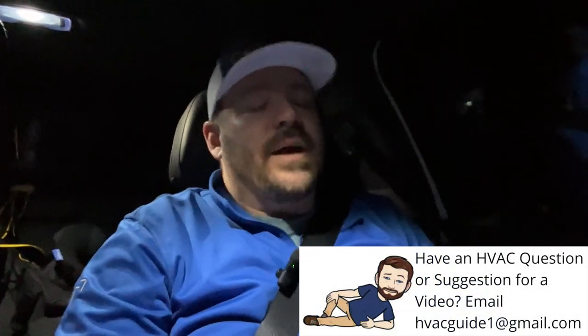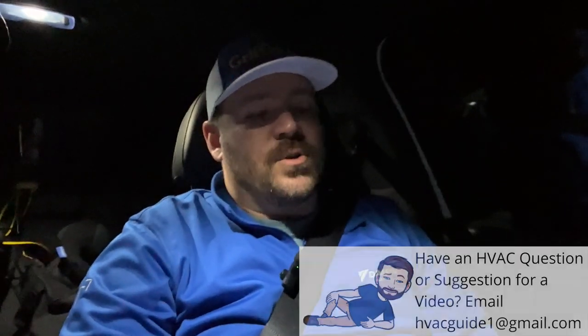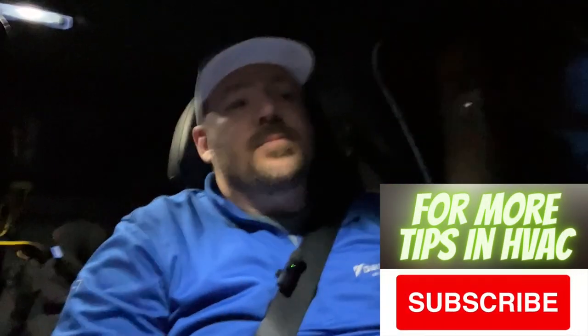I feel like I got a little more technical than I usually do in my videos, but I wanted to explain that. If you're a homeowner trying to figure out setting up your dual fuel system — setting up the programming — or in contrast, setting up a straight all-electric heat pump system, now you know why there are lockouts and why the system needs to turn off the outdoor unit before it can turn on the gas furnace.